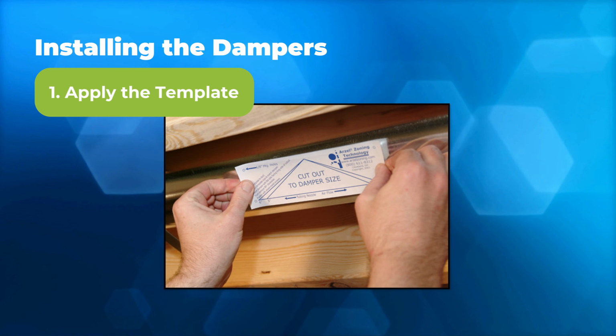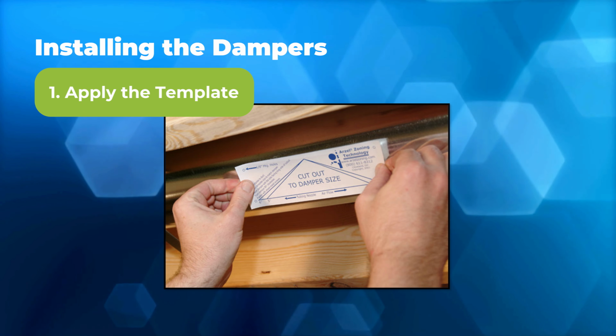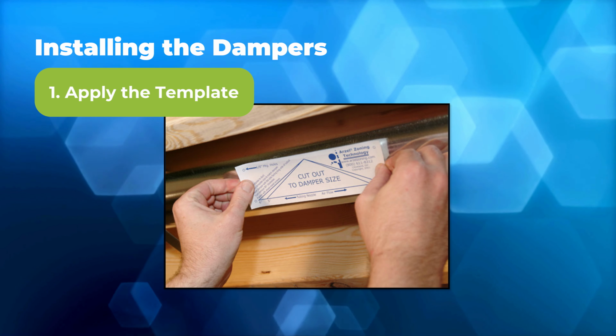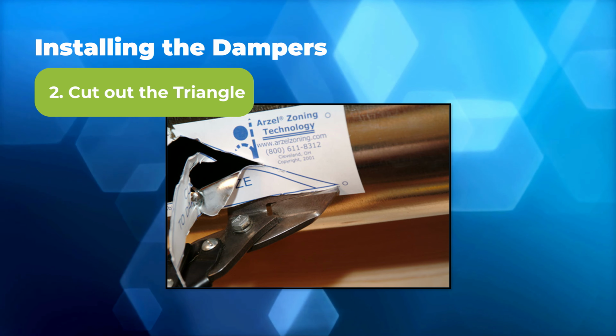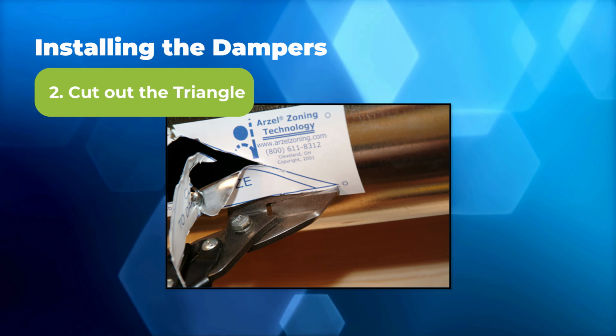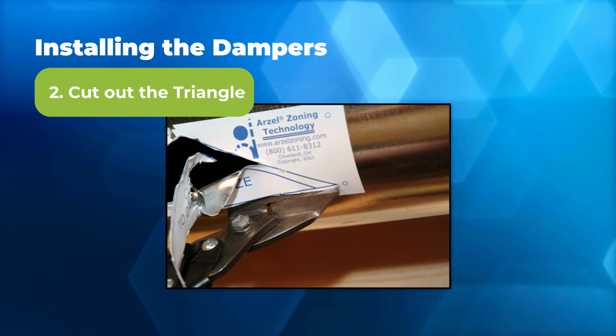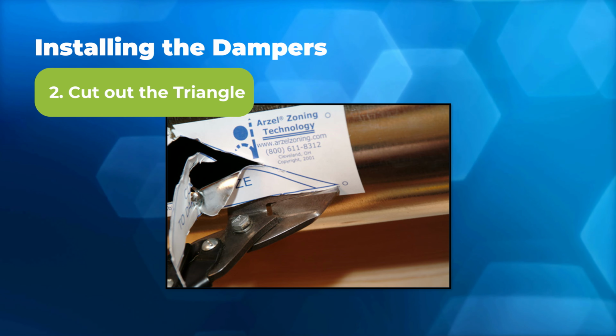If you got a 5 or a 6, it's going to be on the same template. It's going to be a triangle cutout, so you're going to mount it up to the ductwork. And then you're just going to cut that triangle out. Pretty quick. Once you do a couple of these, you can usually do a damper a minute on installation.